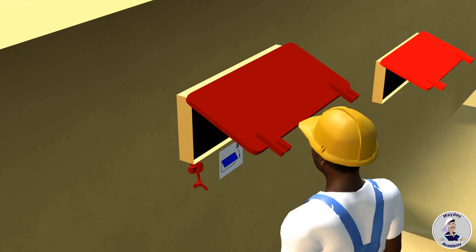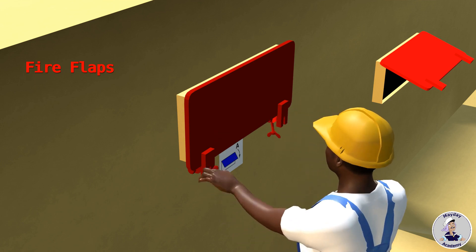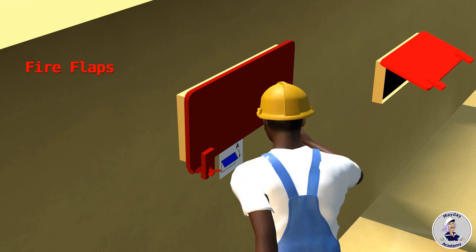Fire flaps and other closing devices are fitted in all inlets and exhaust outlets of the ship's ventilation system to prevent the supply of fresh air to any compartment on fire. Flaps are simple hinge plates that can close off a ventilation inlet or outlet. They are secured with winged bolts to keep the flap in the closed position.